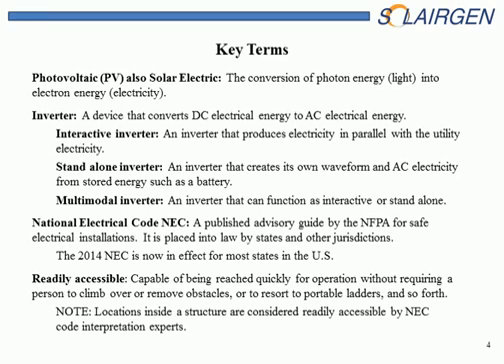We have several different types of inverters. The interactive inverter is one that operates in parallel with the utility, so it pushes power into the utility. Whenever the utility power shuts down, it shuts down with it. A standalone inverter is designed to operate off-grid, separate from the utility. It develops its own waveform and uses the battery bank as its storage and power source. A multimodal inverter is one that can operate either way. So it's basically a standalone inverter that has interactive inverter capabilities.